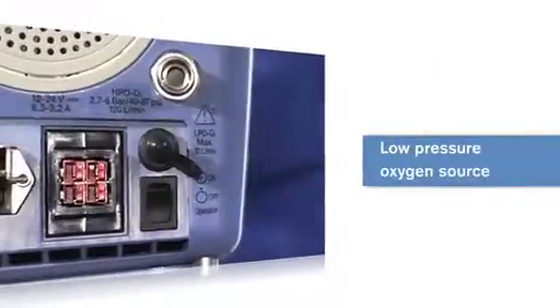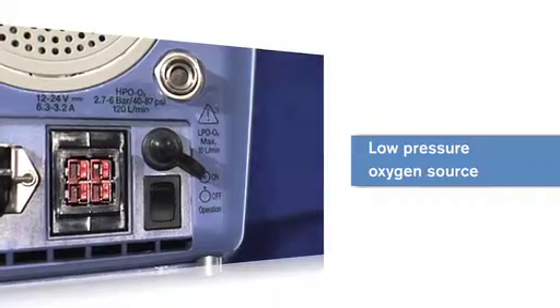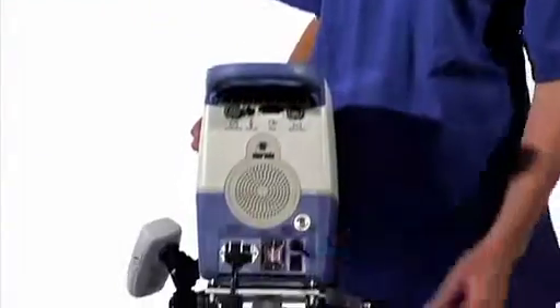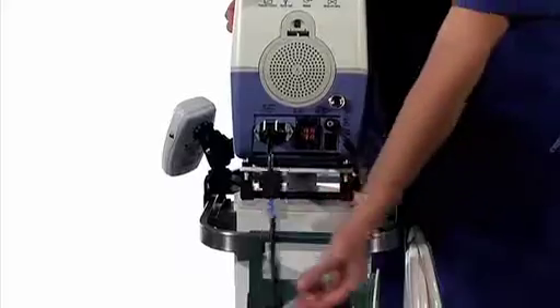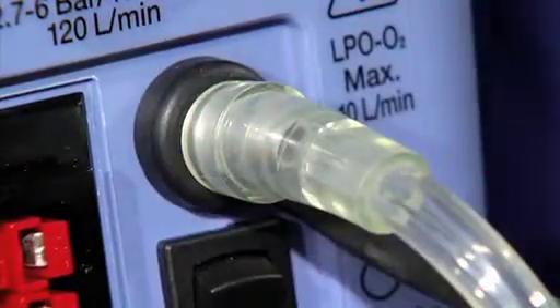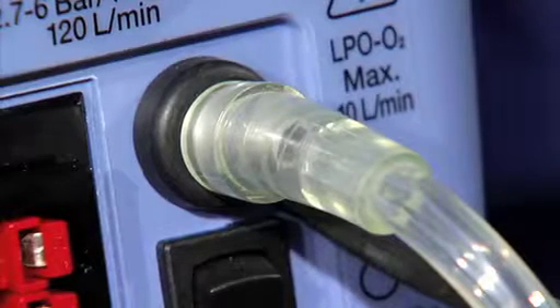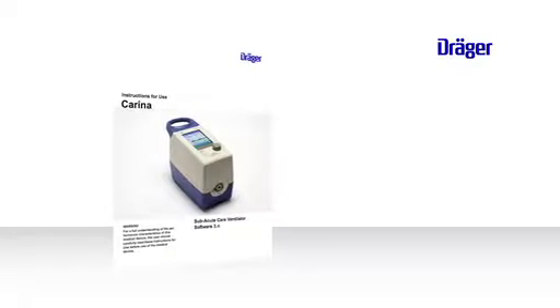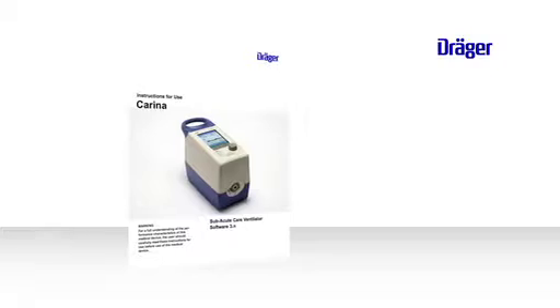It's also possible to use a low-pressure oxygen source. Connect the oxygen supply line from the low-pressure source to the low-pressure inlet. The FiO2 concentration can't be set on the device when using the low-pressure oxygen source. The oxygen concentration needs to be set using the table in the operation chapter in the instructions for use.